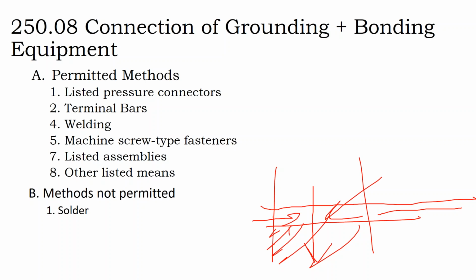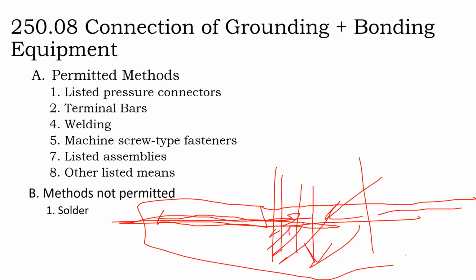And so it was hard to establish an actual reference to ground, where if we were trying to ground fault, the voltage was not actually quickly draining to the ground. And so after driving 3 ground rods into the ground, eventually we had to dig a trench and just bury some copper wiring down into the ground and go well above and beyond the requirements of code, just so that for our specific soil type, we had an effective ground path. And we had to increase the surface area.